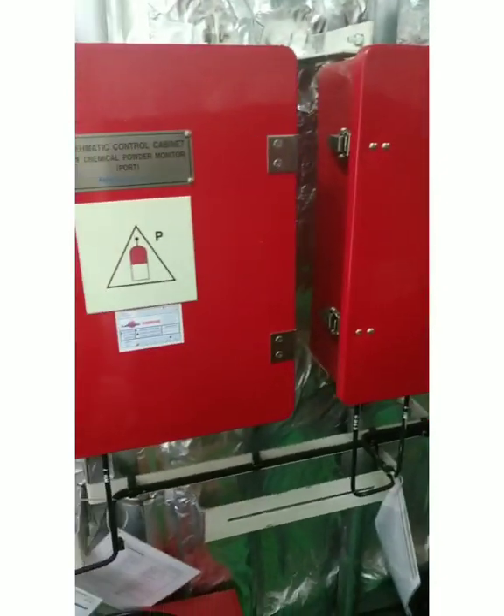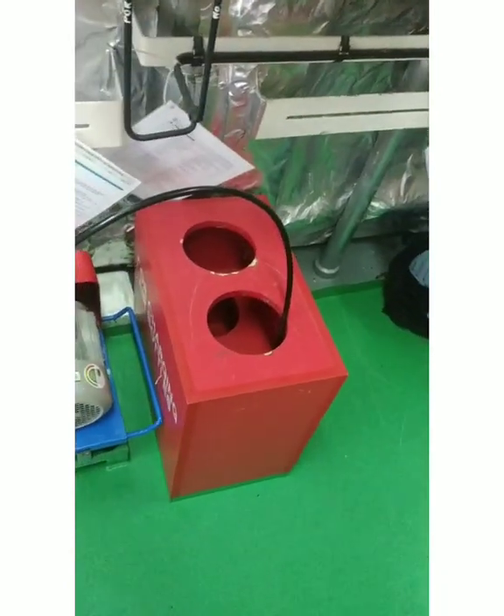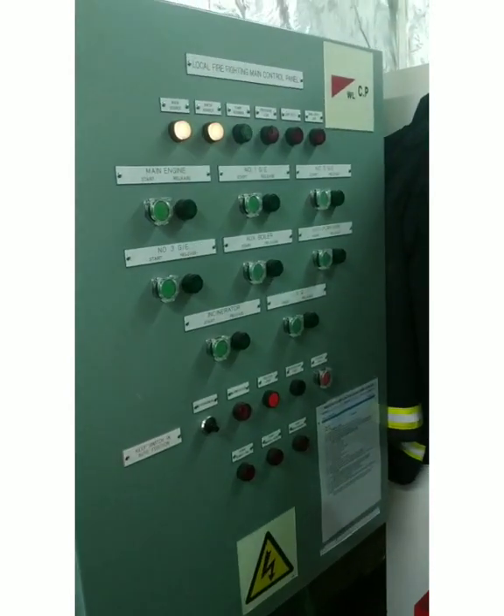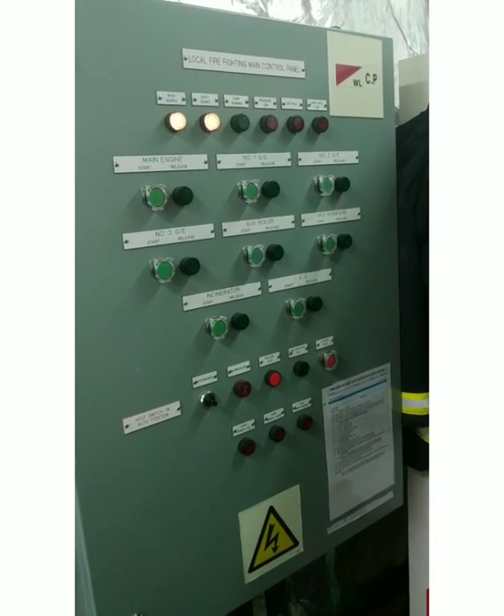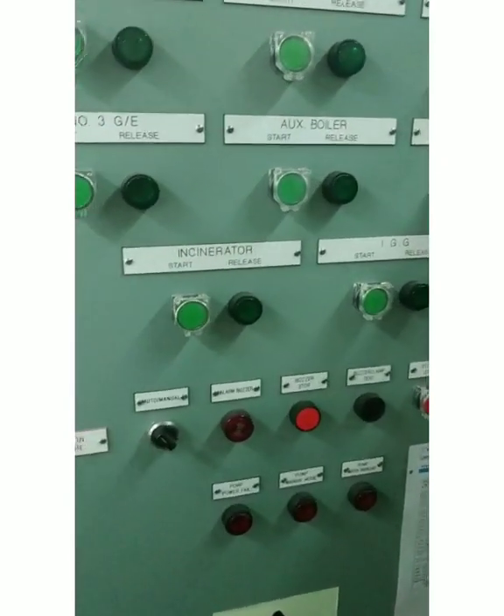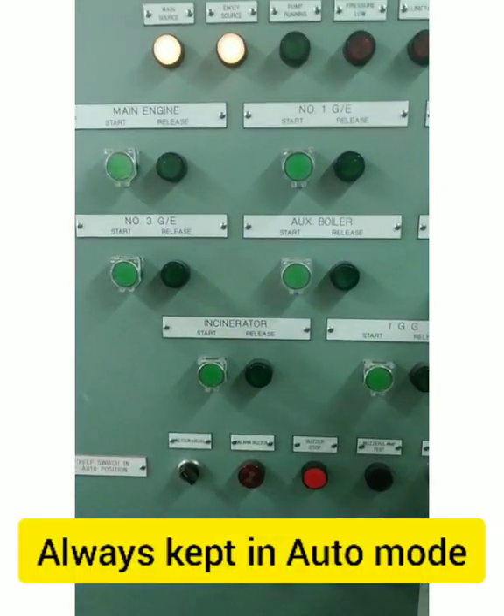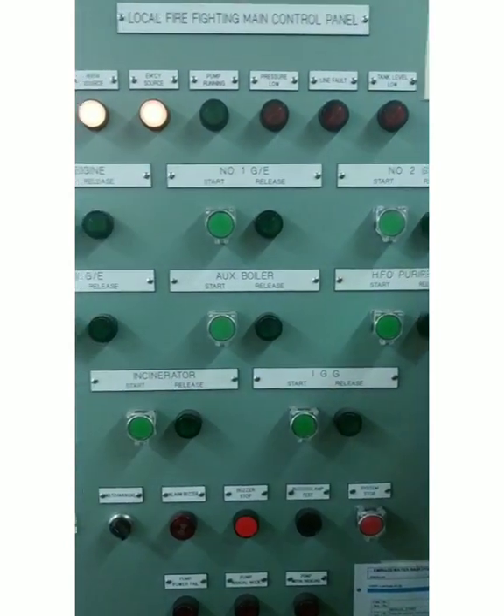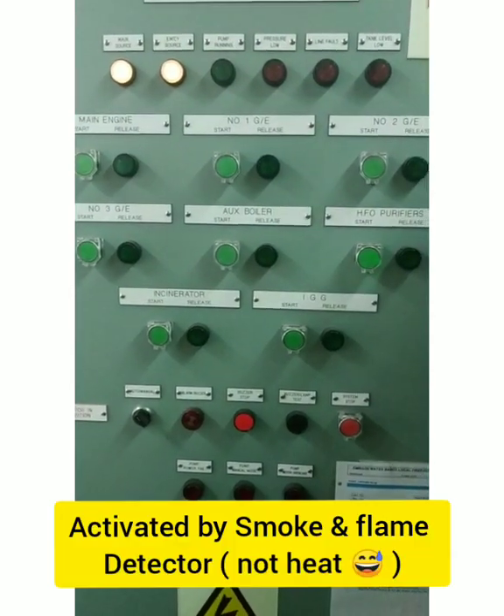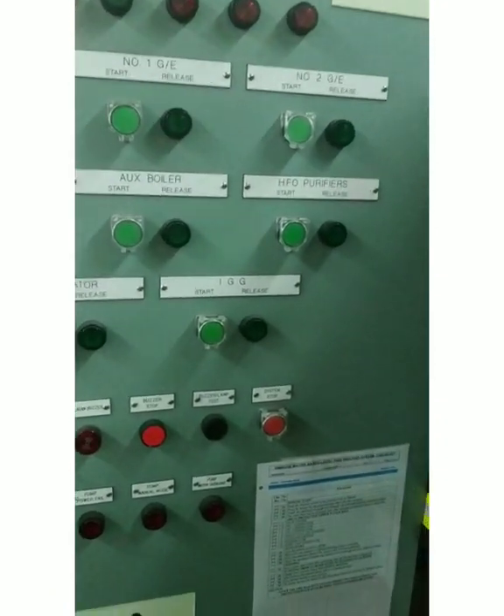I just want to familiarize you with the contents of the EHQ. In this arrangement you can keep the SCBA bottles here for charging. The next thing is the local fire fighting main control panel. This is a hi-fog/high-pressure mist system for the engine room. Make sure it is always kept in auto so that if any unit — main engine, generator one, generator two — is activated by smoke as well as heat, it will activate automatically.